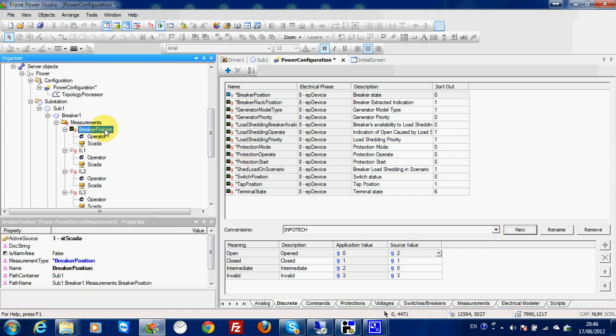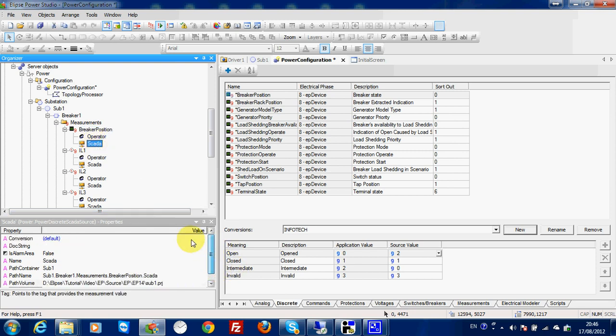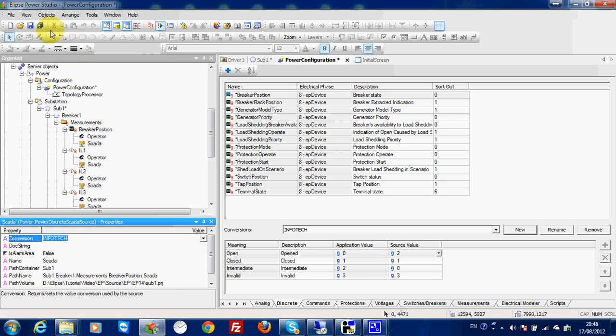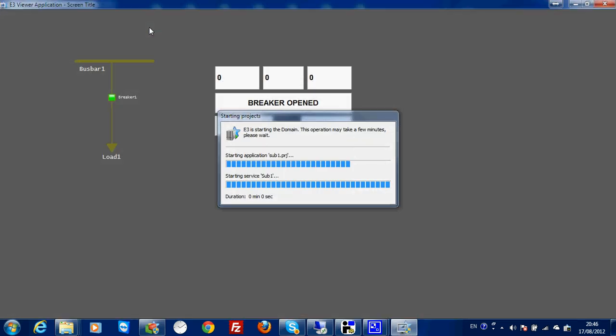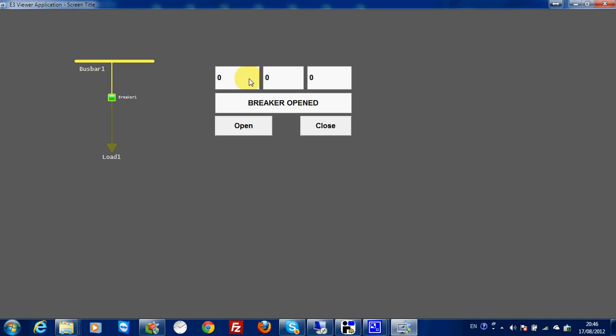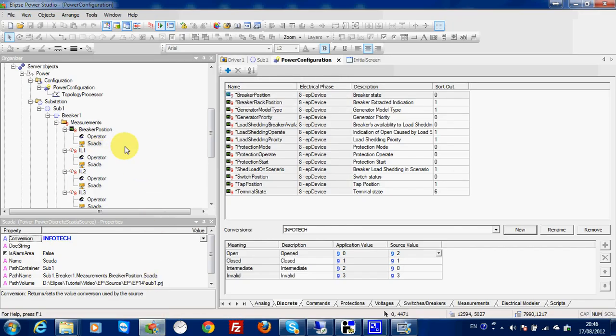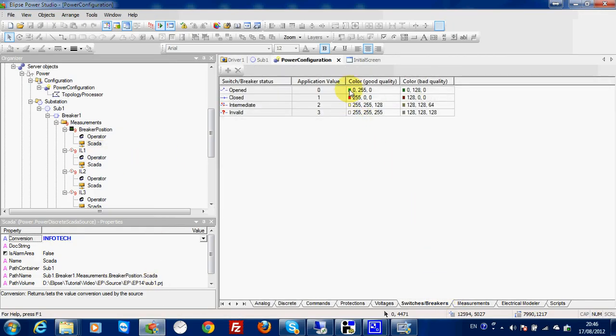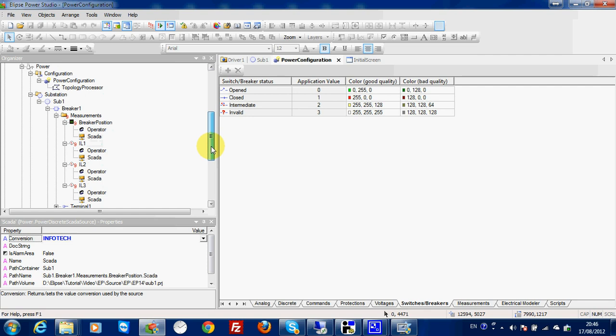Then I go back to the breaker position here. In SCADA, I will choose 'infotech' as conversion. Then I run. The breaker is open. Now, if the breaker is really open, the currents do not pass. If I close, the current goes through. The component is red for close and green for open, which is the same thing I defined here — open green, red close. So everything is perfect for the breaker position.